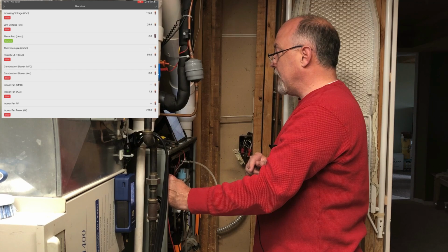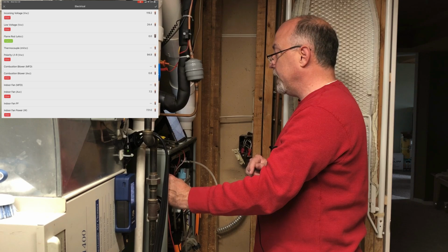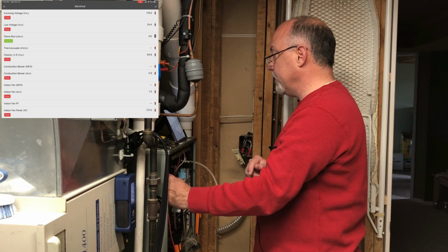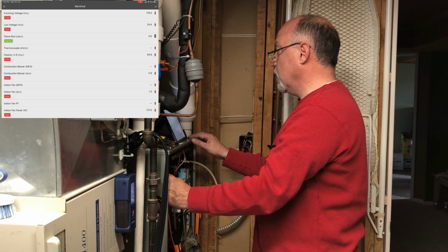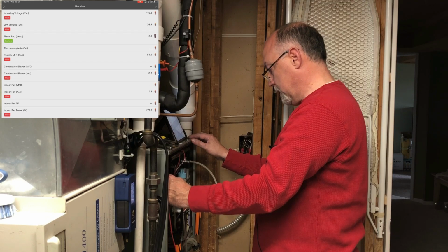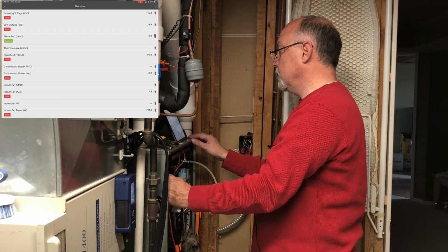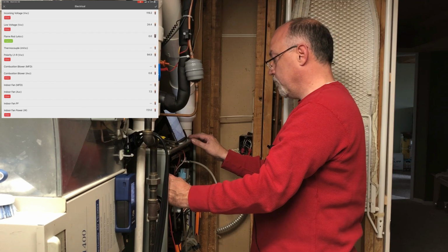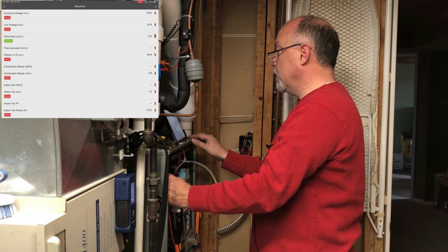So you need to make sure that you've got everything held on tight, because if you don't, you're not going to get a good reading, and the burner will just shut off again. We'll hear it go through its spark ignition here in just a second. Going through a little post-purge here, pre-purge, so it takes a few seconds for it to go. Holy cow. There we go.